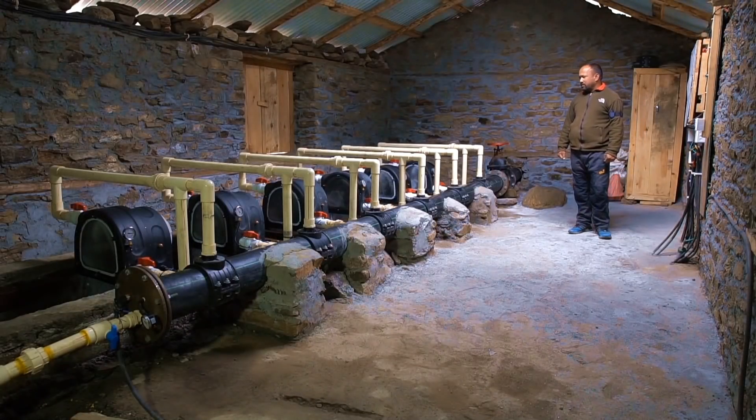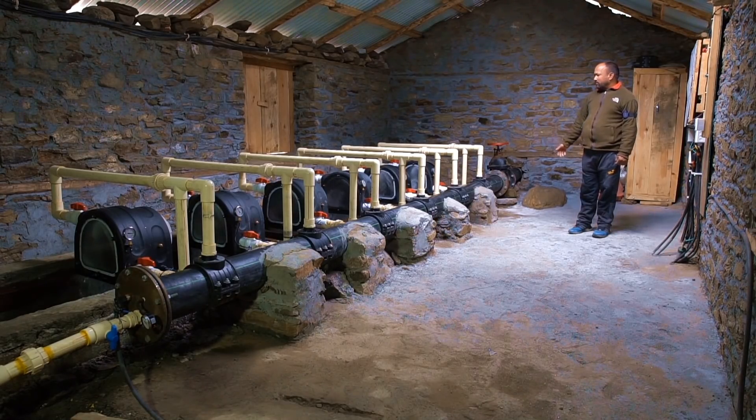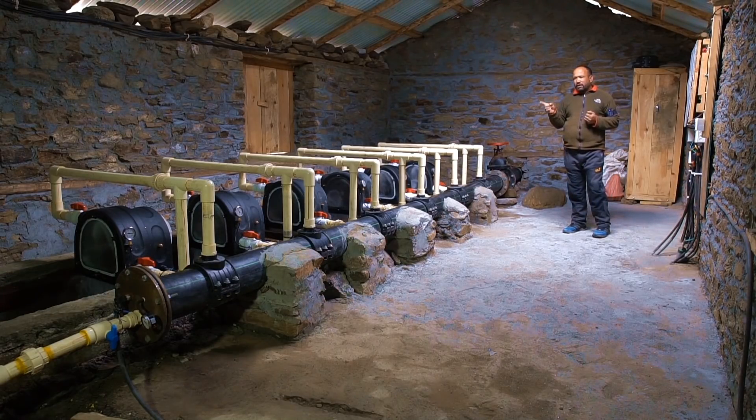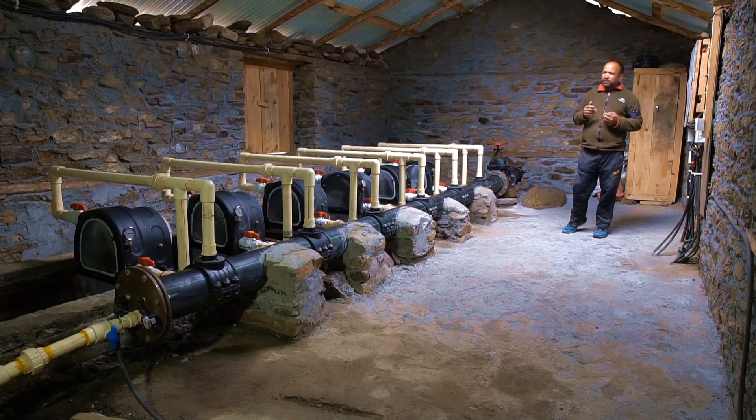The Mohari Village Hydro Power Plant is a modular pico-hydro power plant with six Pelton turbines — the first of its kind in Nepal. The efficient, lightweight, and easily maintainable Pelton turbines use runners with multiple permanent magnet poles, housed in recycled plastic housing bodies. Though only one turbine would meet the village's power demand today for all basic indoor lighting and phone charging, we installed six turbines to prove the concept of modularity — meaning the hydropower plant can grow along with the village's power demand, from initially one turbine up to 10 turbines, with the same infrastructure already in place today.